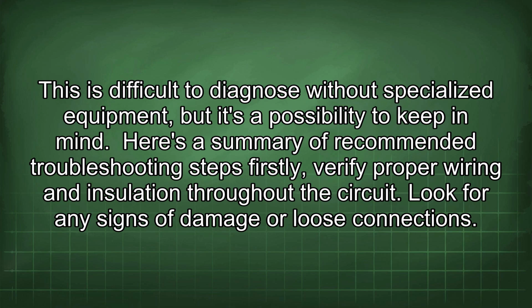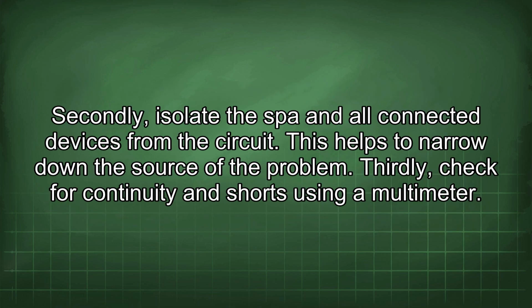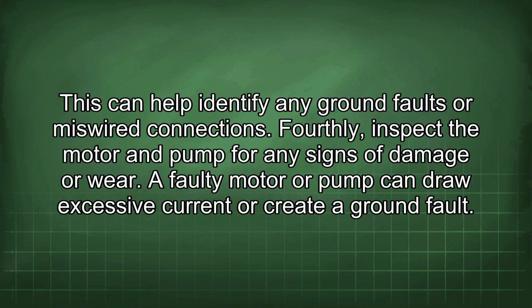Here is a summary of recommended troubleshooting steps. Firstly, verify proper wiring and insulation throughout the circuit. Look for any signs of damage or loose connections. Secondly, isolate the spa and all connected devices from the circuit. This helps to narrow down the source of the problem. Thirdly, check for continuity and shorts using a multimeter. This can help identify any ground faults or miswired connections.